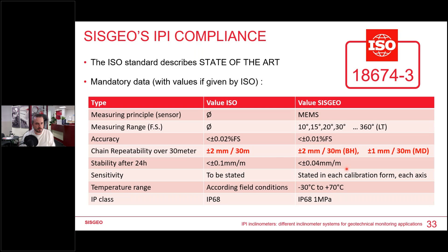Sensor technology. As I said, we provide individual calibration for each probe or tiltmeter that is coming out from the factory. We use accredited test benches. We compare directly with the references, so the official references, so an accreditation office comes to us in order to validate the system. We define some steps, we obtain a table, and from this table we interpolate in linear and polynomial, and we calculate the error from the theory to the sensor. The sensor is compliant if the error that we get is lower than what we state in the datasheet. So that means when you purchase a system from us, it's at least better than what we are stating in the datasheet. It's always better than that. So it cannot be worse. If it's worse, we just throw the sensor away.